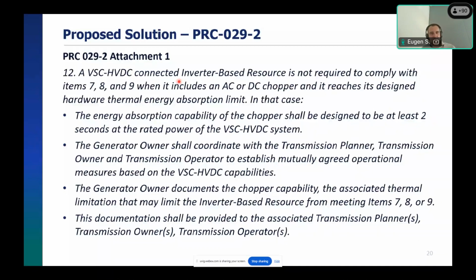So there is also a suggestion for the chopper design, meaning 2 seconds of the rated power of the VSC HVDC system. These 2 seconds are what is widely used by the industry. And also, this capability needs to be documented accordingly so that everybody is aware of those limitations.